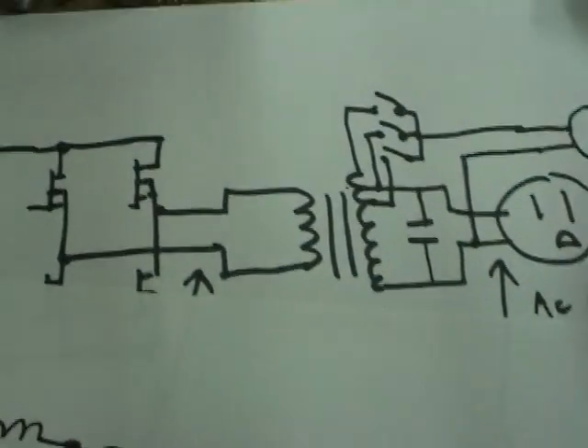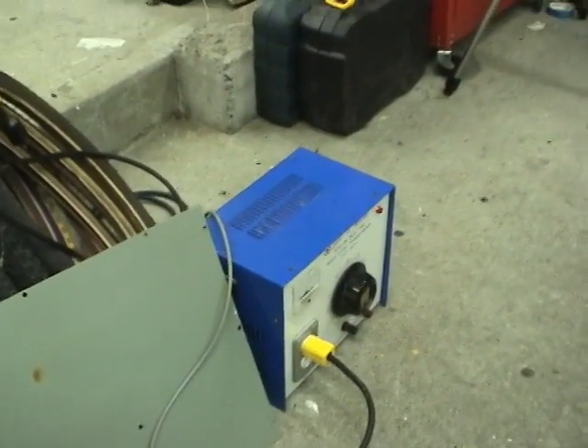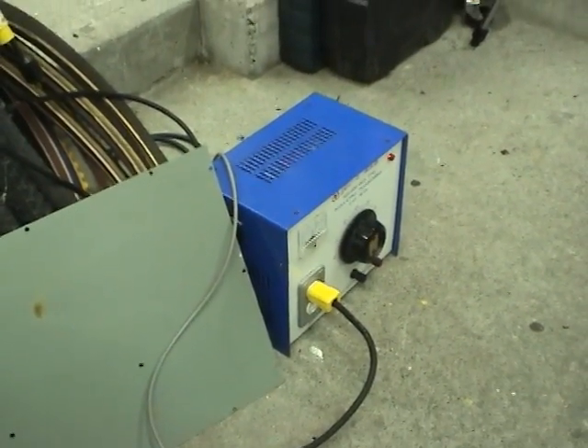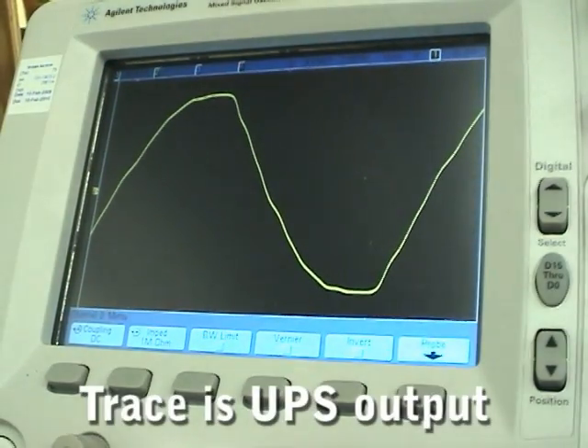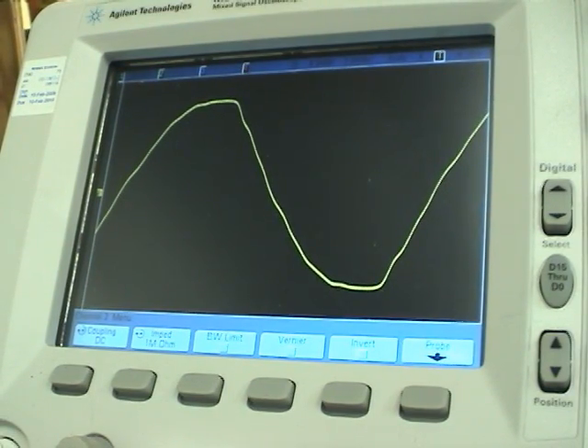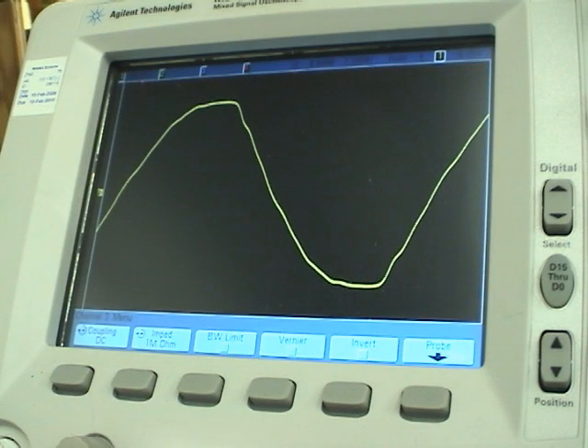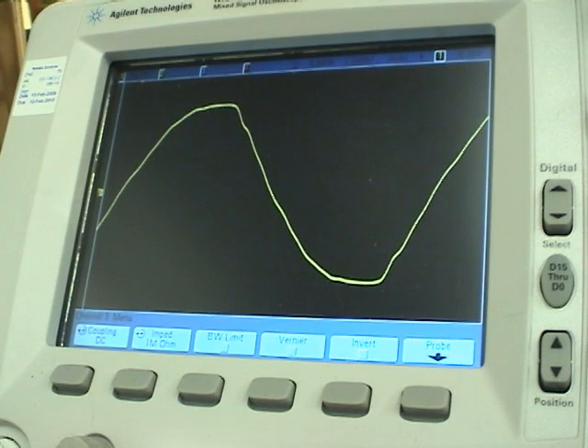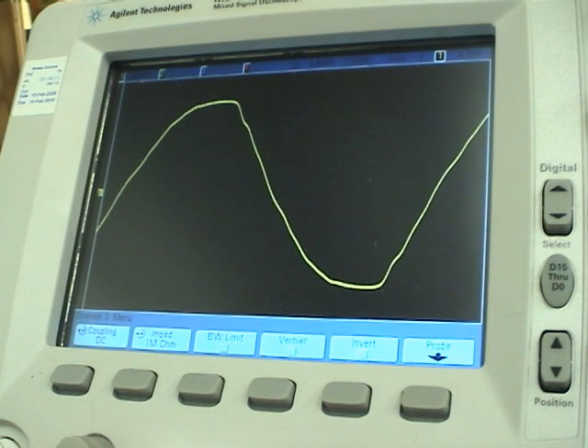And I'll demonstrate that right now. What I'm going to do here, is turn down the variac, and then turn up the variac, and show you how the unit switches taps to adjust the voltage. I'll just set this in the scope. This is regular 208 volt in. And as we decrease it, you can see the amplitude decreases, and eventually, the UPS will turn on, and then switch the relay over, and then turn back off again. There we go. That just switched.